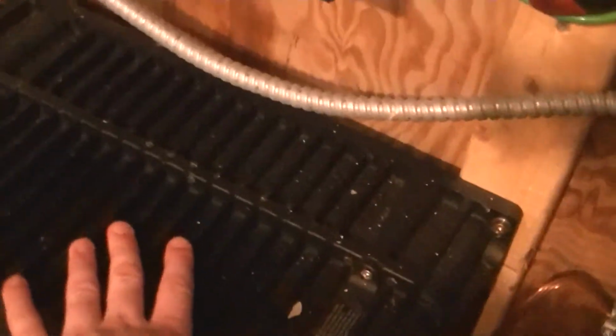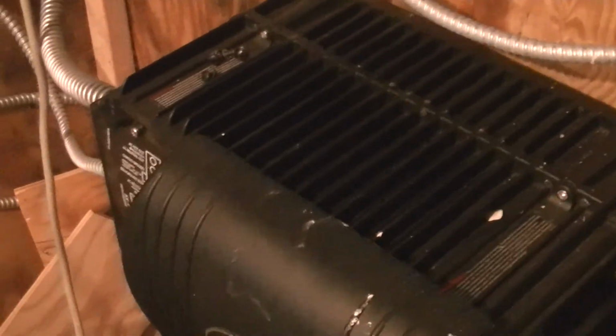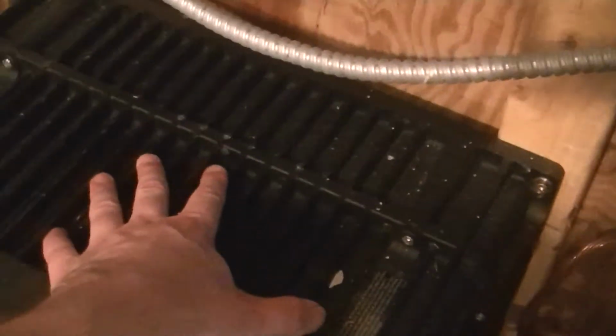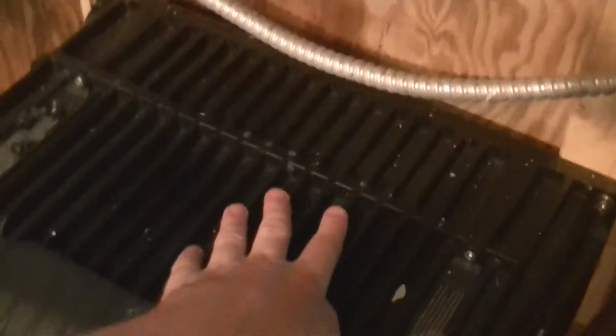Thus the rather heavy duty screws and the rack holding it in. So I guess technically this could qualify as a transformer thing, but really the transformer in this case is integrated into a larger device. Of course, it also means that these are much more expensive. This one was about $1,800. This one was under $200. Well, actually, technically $199 and $1,798.